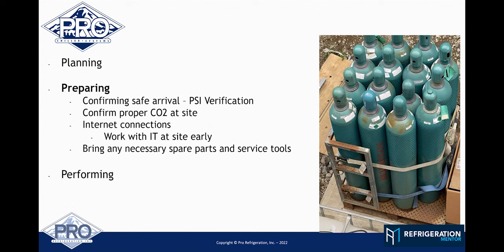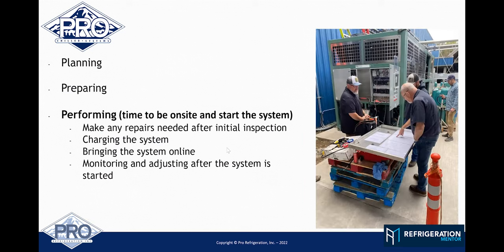Then we get into the performing side, and this is where it's time. Now you're on site and you're ready to start that system up. Make any necessary repairs after your initial inspection. We did end up having to fix it. We shipped the system with a 35 PSI nitrogen charge, and it showed up dry. We got on site, started to isolate sections of the system, and found some threaded connections right off the bat that needed to be tightened down. There was nothing on the welding side or the brazed joints.